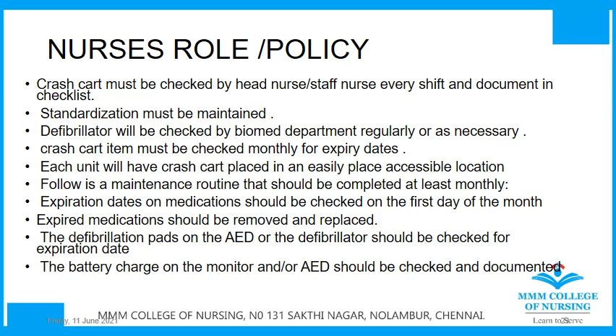Each unit will have a crash cart placed in an easily accessible location where an emergency may arise. Follow a maintenance routine that should be completed at least every month. That is, check expiration dates on medications, and expired medication should be removed and replaced with medications which are not expired. The defibrillation pads on the AED or the defibrillator should be checked for expiration date as well. The battery charge on the monitor and the AED should be checked and documented every day on the checklist in each shift.